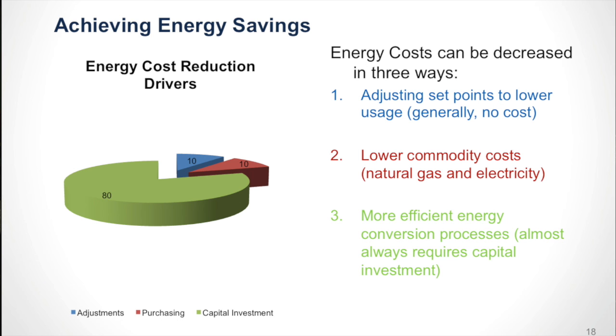What I find is that we can impact their costs about 10% by just doing adjustments, whether that's condensing temperature on a cooling tower, chilled water temperature, or lowering thermostats. That can have about a 10% decrease on your cost.